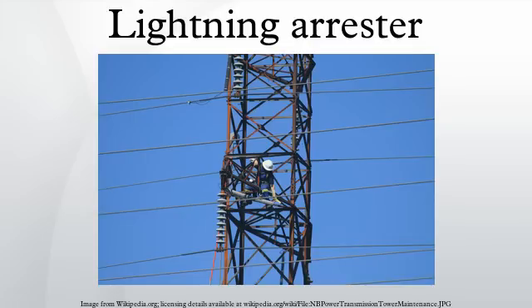A lightning arrestor may be a spark gap or may have a block of a semiconducting material such as silicon carbide or zinc oxide. Thyrite was once a trade name for the silicon carbide used in arrestors. Some spark gaps are open to the air, but most modern varieties are filled with a precision gas mixture, and have a small amount of radioactive material to encourage the gas to ionize when the voltage across the gap reaches a specified level. Other designs of lightning arrestors use a glow-discharge tube connected between the protected conductor and ground, or voltage-activated solid-state switches called varistors or MOVs.